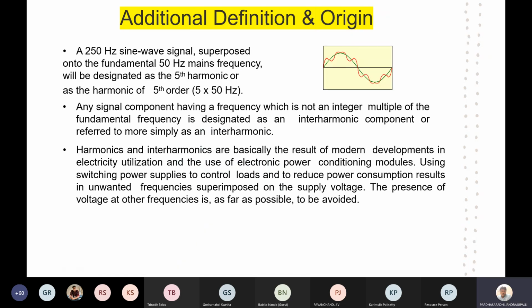Further, I would like to bring a simple explanation to you. Here, this is the pure sinusoidal wave, let it be at 50 Hz. A 250 Hz sine wave signal, which is superposed onto the fundamental 50 Hz main supply, will be designated as the fifth order harmonic, or the harmonic of fifth order. Any signal component having a frequency which is not an integer multiple of the fundamental frequency is designated as an interharmonic component, or referred to more simply as an interharmonic.